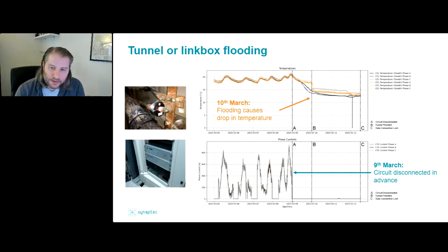What happened in this case was the operator actually did a preventative step and disconnected the circuit on the 9th of March this year. Then on the 10th of March is when our sensors detected the flooding due to the drop in temperature. A couple of days later, the entire substation was flooded, so we lost the connection to our cloud data service, and that's basically when we lost data.